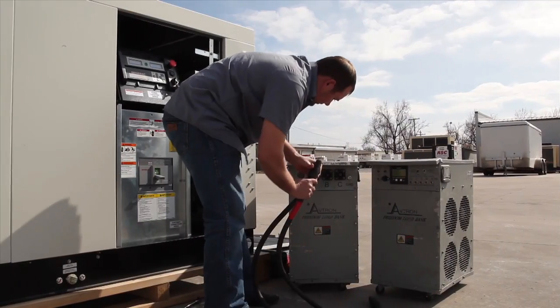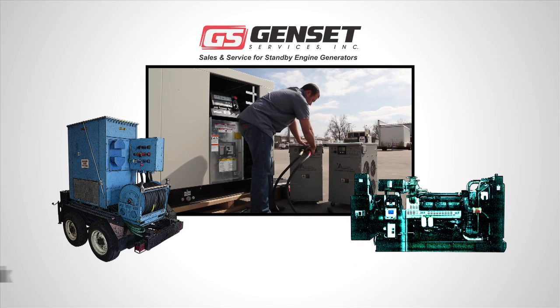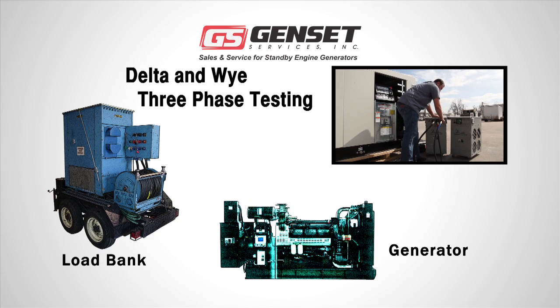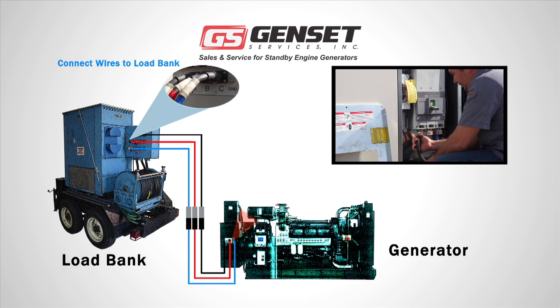Load banking can be part of the usual planned maintenance contract. An experienced technician brings to the generator set a mobile load bank rated to carry the required load. Our technician carries out the recommended NFPA 110 4-hour test. After verifying suitability for the load banking procedure, the technician first connects the wires to the load bank, then connects the wires to the generator circuit breaker.